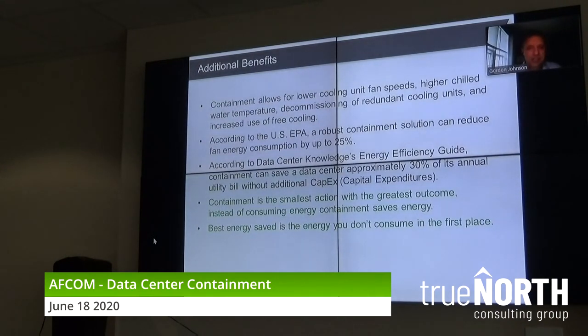It says, according to Data Center Knowledge's Energy Efficiency Guide, containment can save a data center approximately 30% of its annual utility bill without additional CapEx. Now, some people might say, well, isn't installing containment additional CapEx? I'm not going to argue that, yes or no, but what we typically see is that number, 30%. It's not unusual for us to hit 25 to 28% savings.